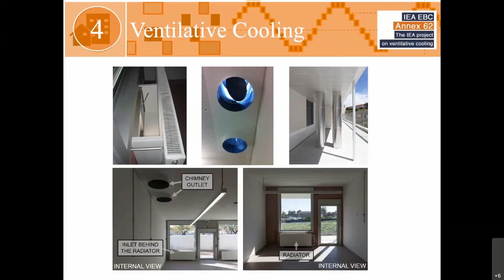Now, time is flying. In the design of these systems, we used detailed EnergyPlus simulation, and this is the result. We focused on low levels of exceedance of the optimal indoor temperature of 26 degrees, looking at how many hours we expected the indoor space to be above that. We also looked at CO2 levels in the rooms and whether these exceeded the regulatory limit of 1200 ppm, with an exceedance possibility of up to 1800.